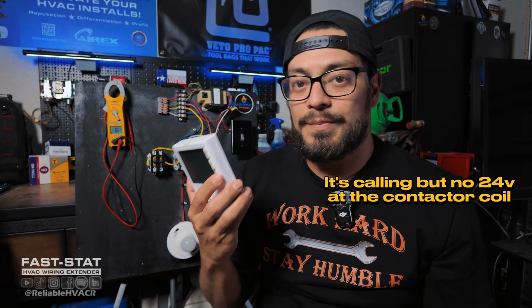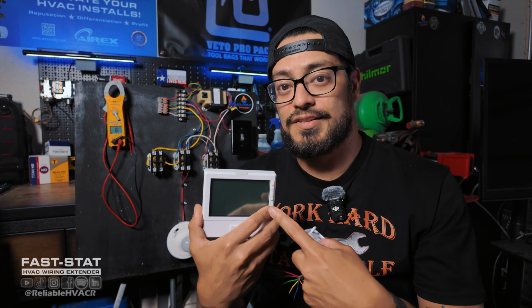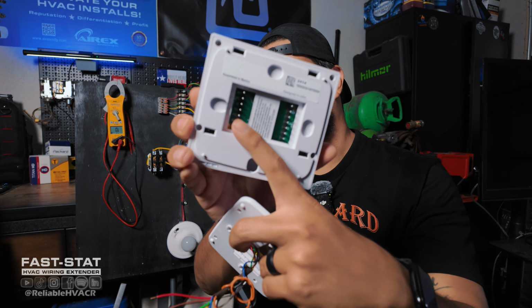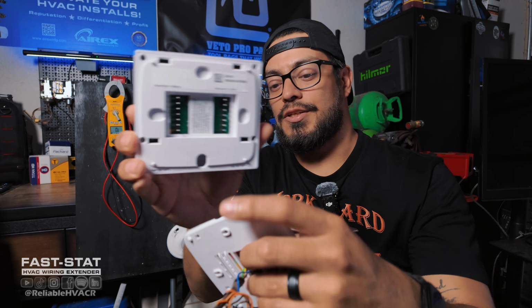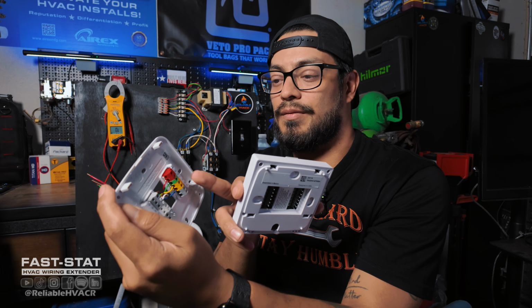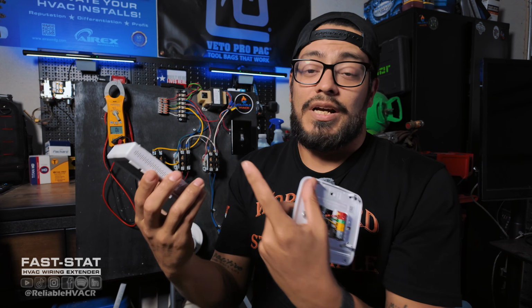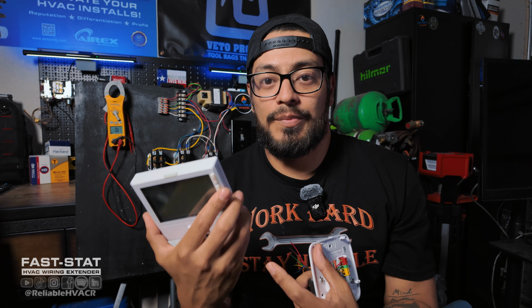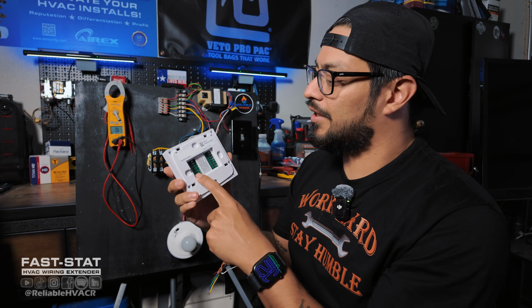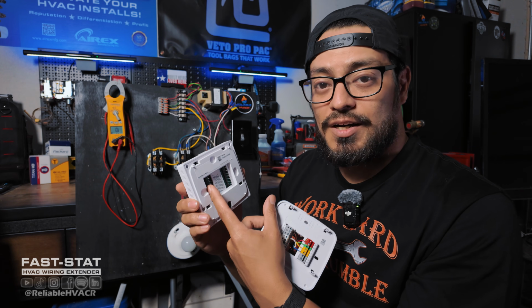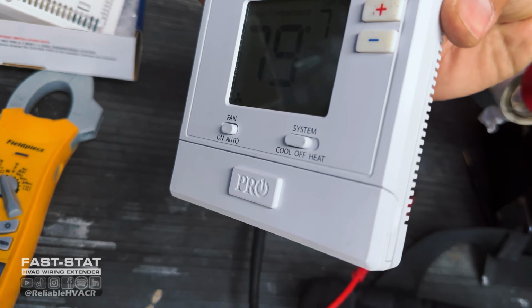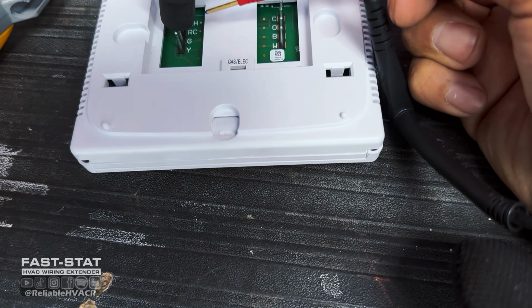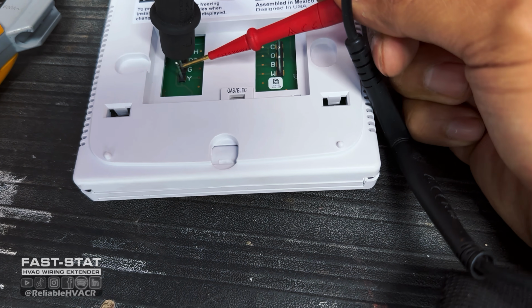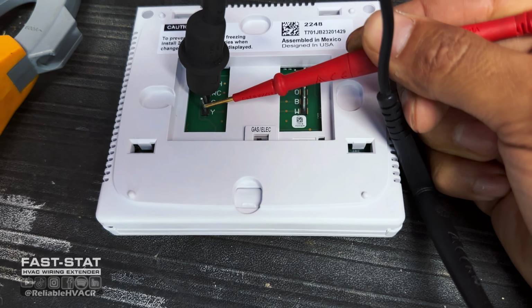Now, if it's battery powered, it's a lot easier, because once you pull it off, it still is calling. And these are the little terminal connections on the back that make contact with the wall plate. I do run into a lot that are battery powered. So if you pull it off and it's still calling, you can start checking with continuity and making sure these contacts are closed. I've had thermostats that do not close their switches, and I go from R to Y1 for cooling, and it never closes. It never gives me that tone. So then I know this thermostat's bad and I'll change it out.